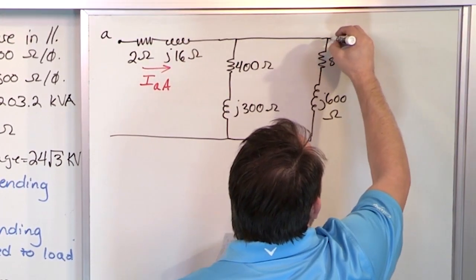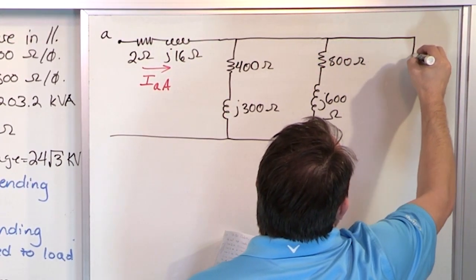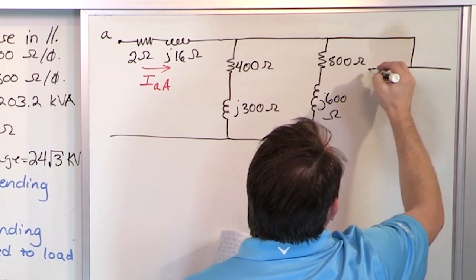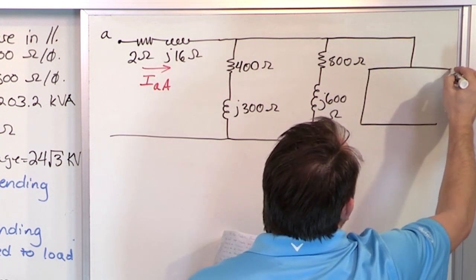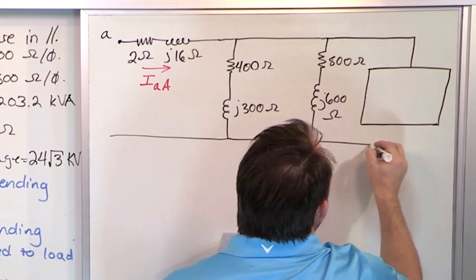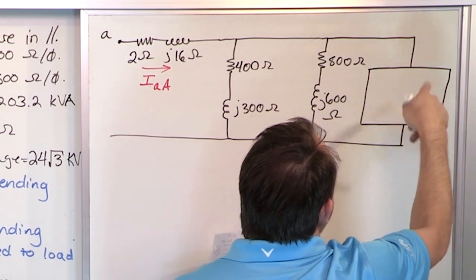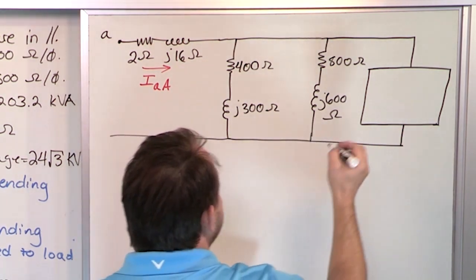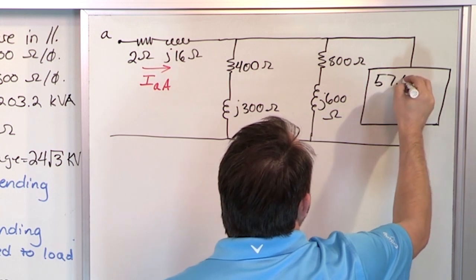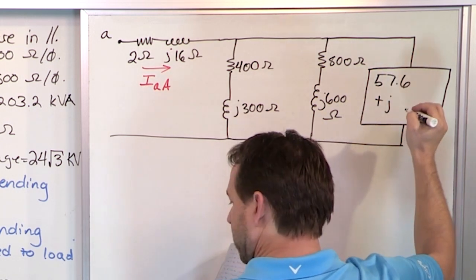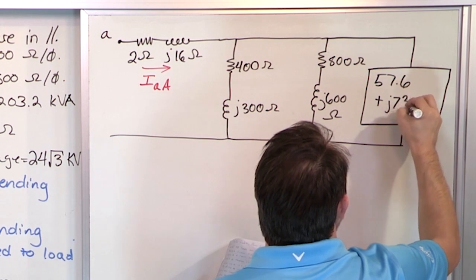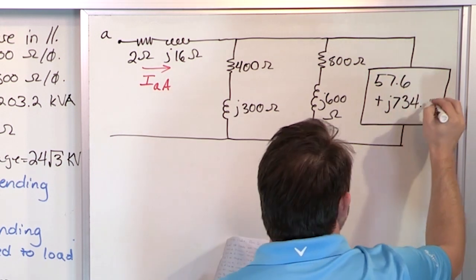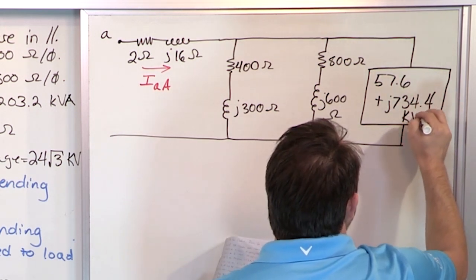What I do is come off in parallel, because we know it has to be in parallel, and draw a box. I don't know what's inside the box — it could be a delta, it could be a Y, whatever. It could be hamsters running around in a circle. But what I know is that it is 57.6 plus J734.4, and that's kilovolt-amps.